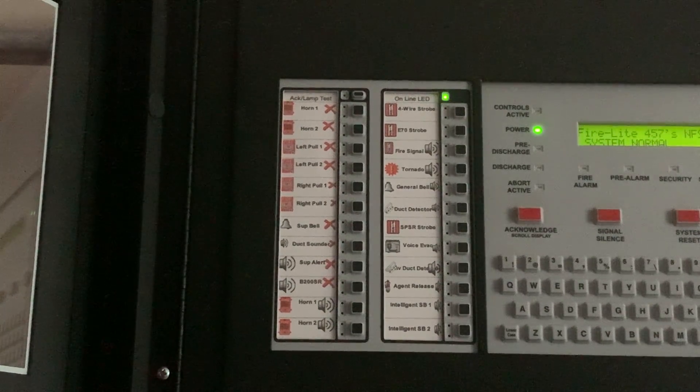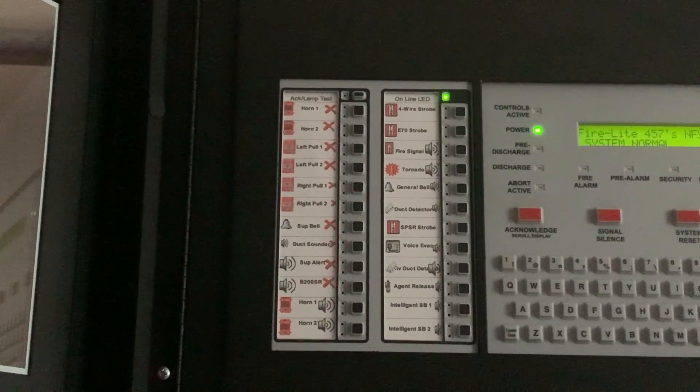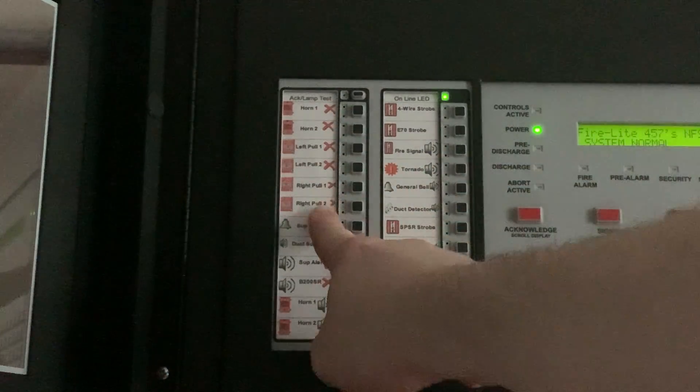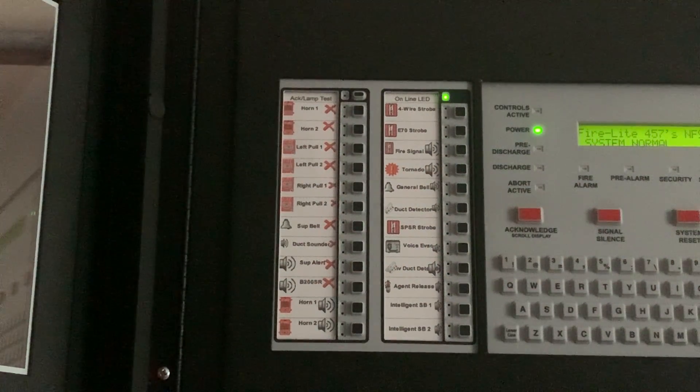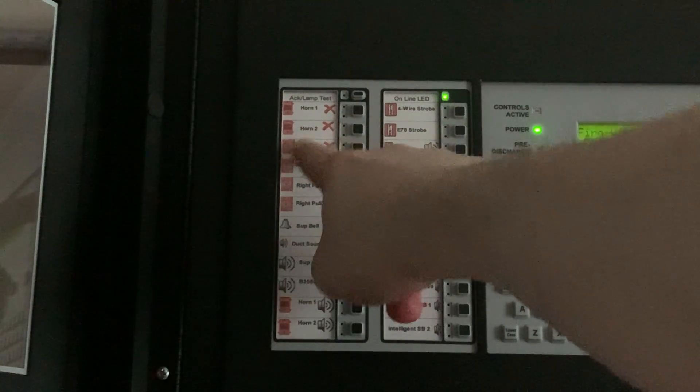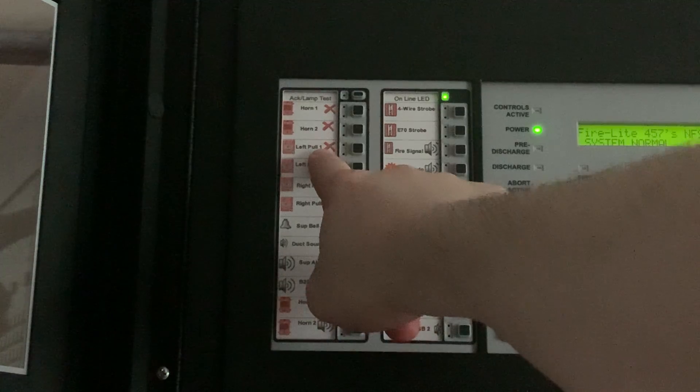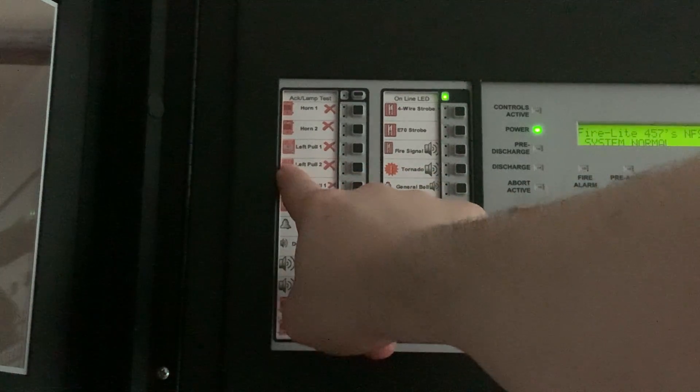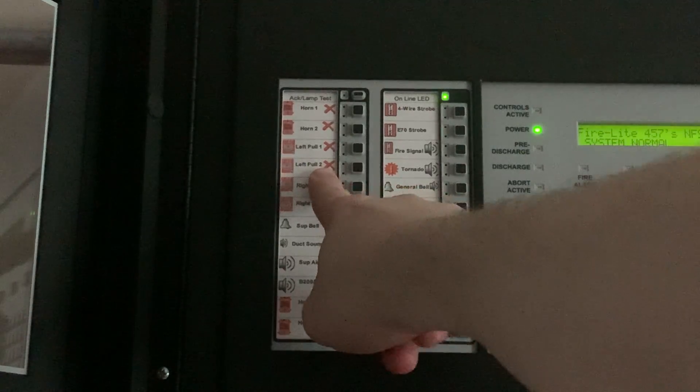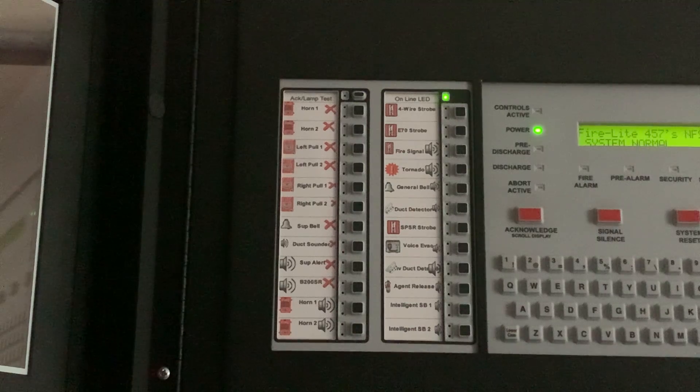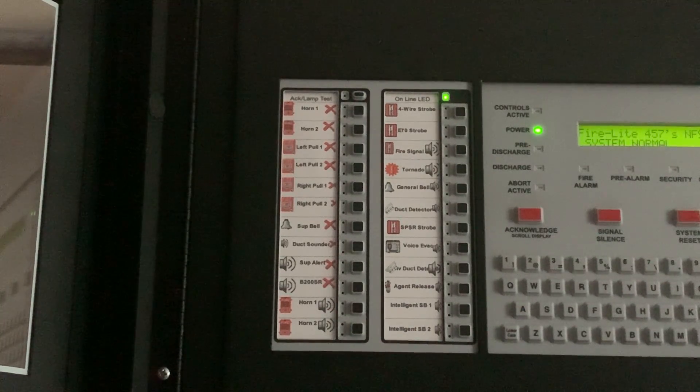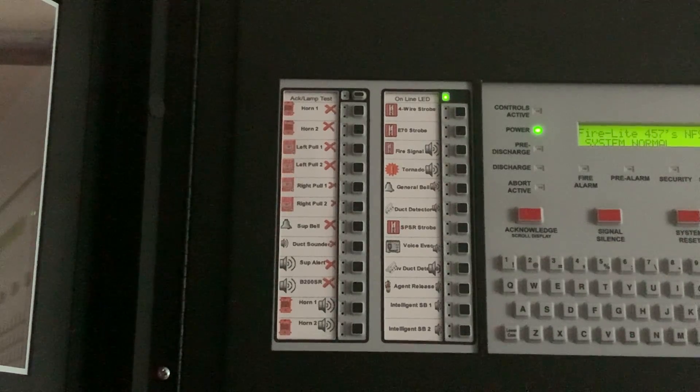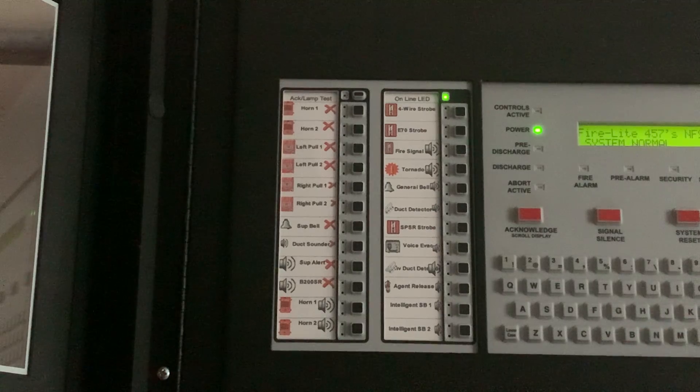Okay, now we're going to go over the ACM24AT and what each function does. So see all these right down here with all the Xs, those are disabled switches. So I have NAC1 disabled, NAC2 disabled, left pull 1 disabled for when I change it out, and left conventional pull number 2 disabled. So that way I can easily change out the conventional pull stations for system tests without having to go into programming, which is very nifty for this ACM.